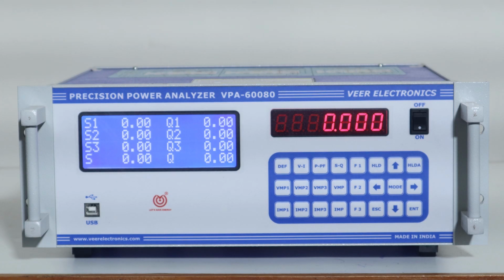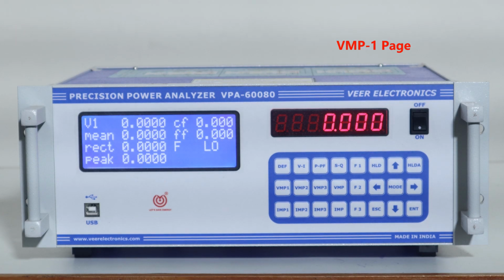Now press VMP1 page button. It shows R phase individual RMS voltage, also shows mean, rectified and peak value for R phase voltage. It also shows crest factor, form factor and frequency.